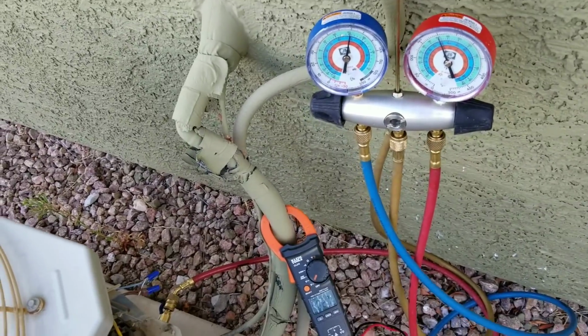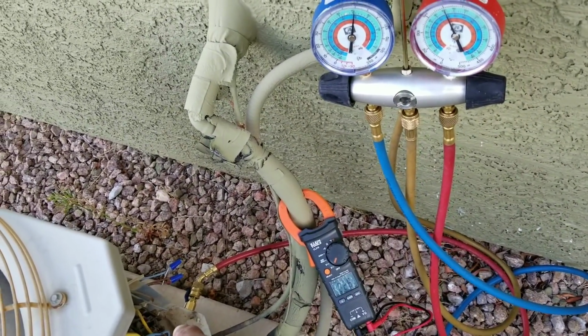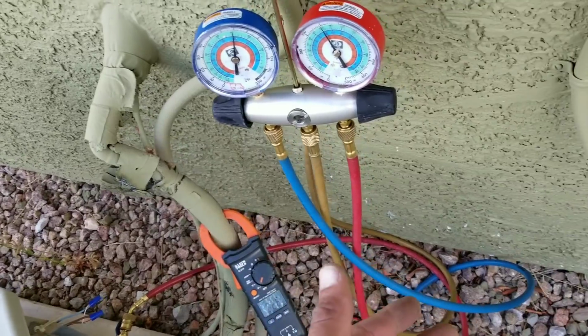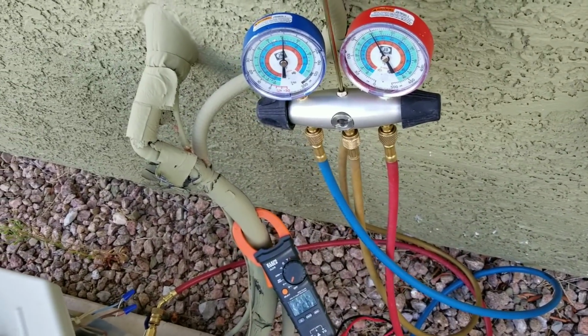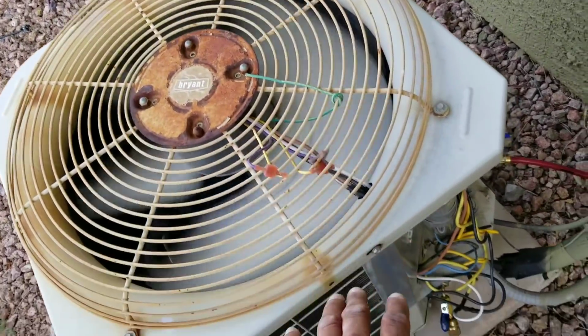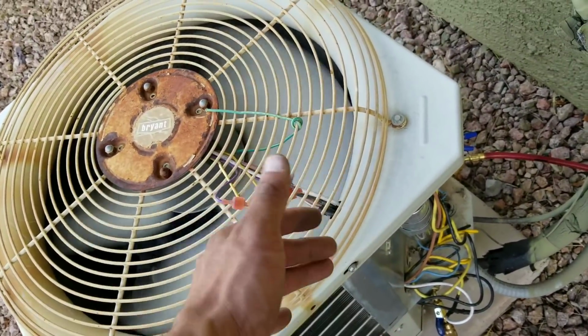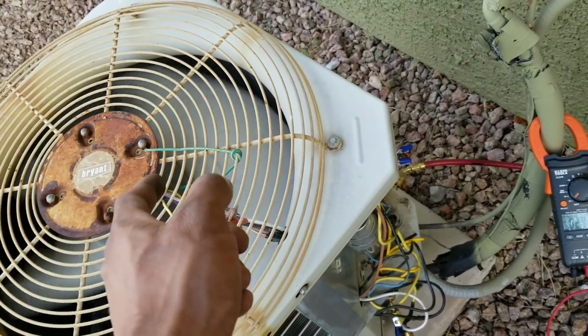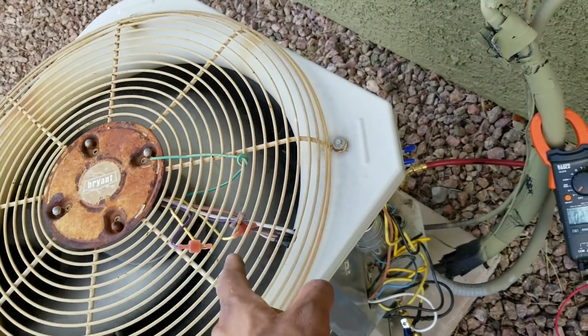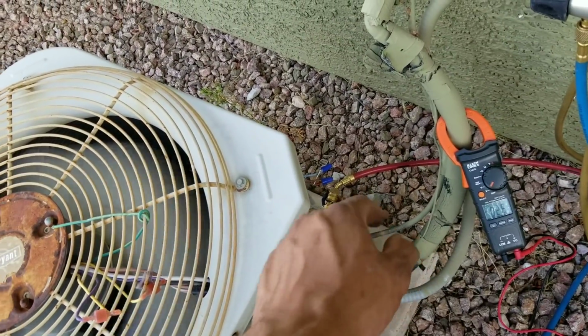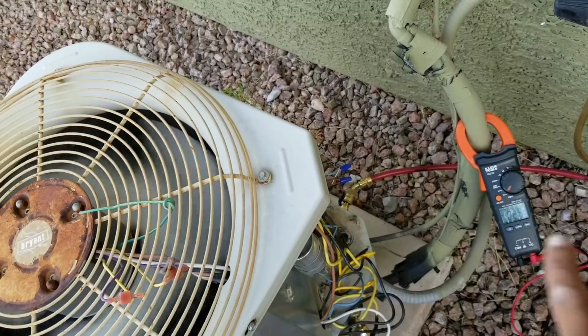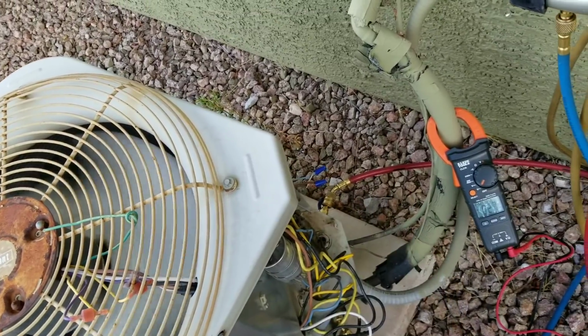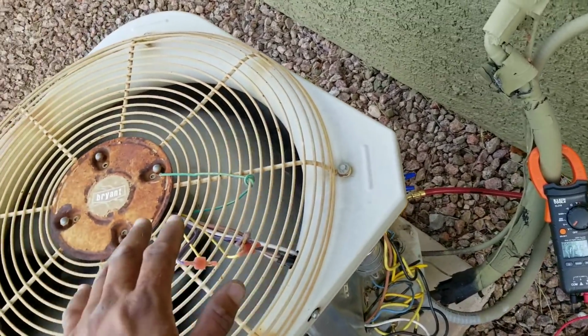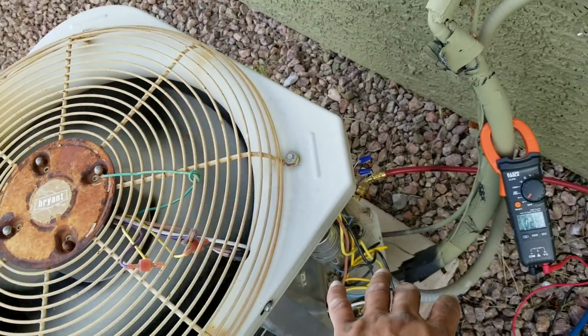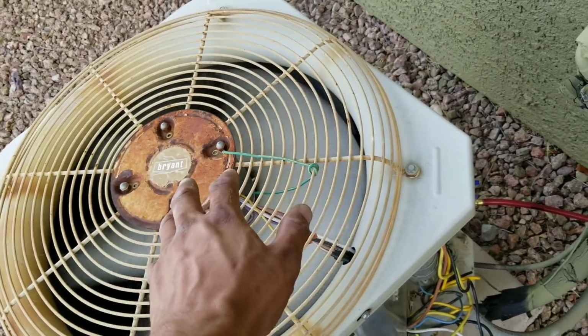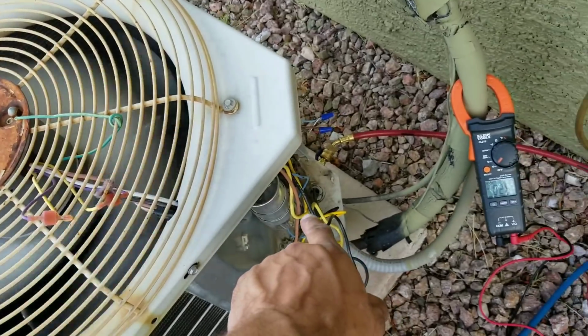There may be a time where you come and your contactor may not be engaged because the thermostat's not set. You'll press the contactor. You'll want to see if your fan motor and your compressor turn on. If they turn on, then you know that the problem is going to be sending the voltage back to the condensing unit. It's usually going to be the low voltage. If you have, let's say, another scenario, you come here, you press your contactor, and your fan motor doesn't start, but you hear the compressor, obviously you know that your fan motor is going to be the issue. It may be your capacitor.